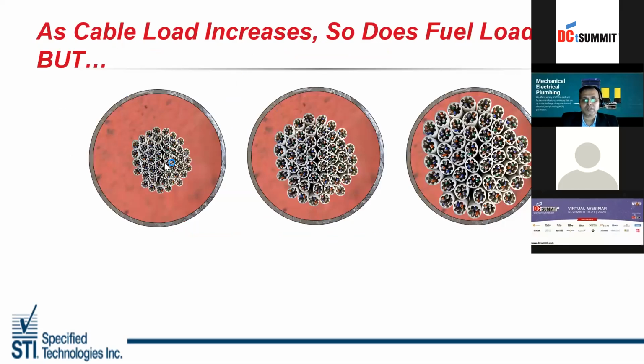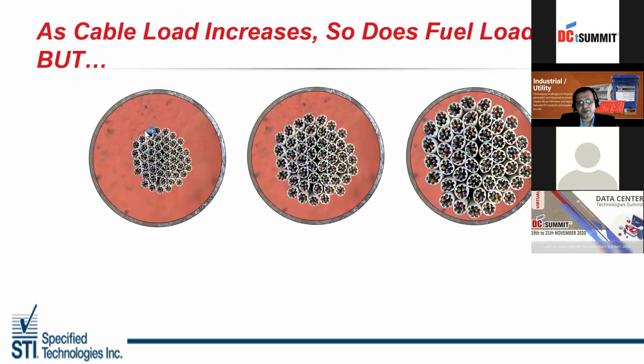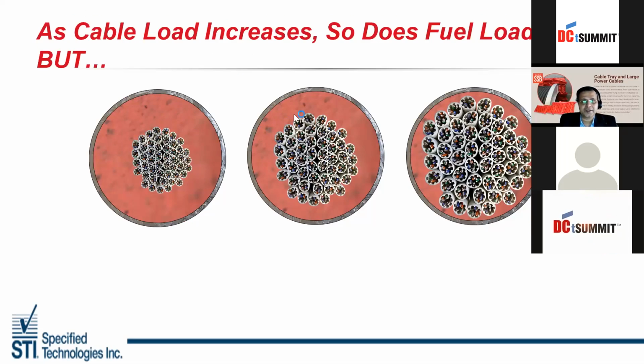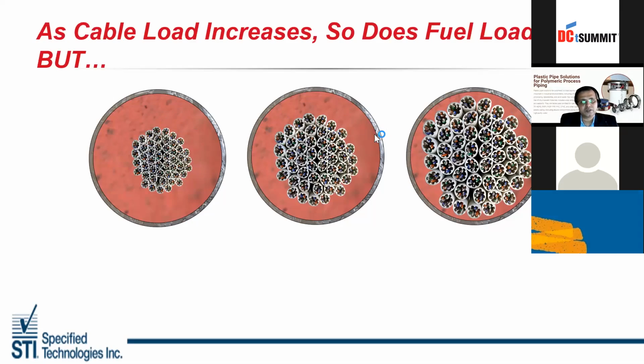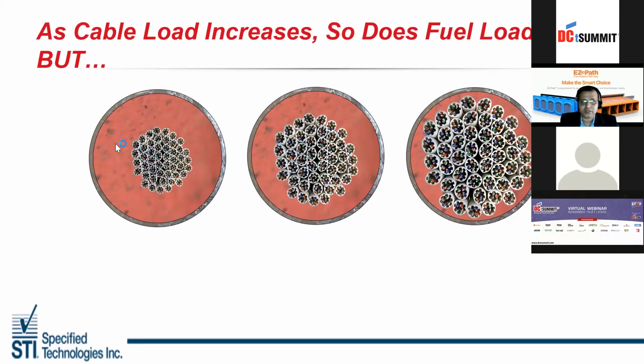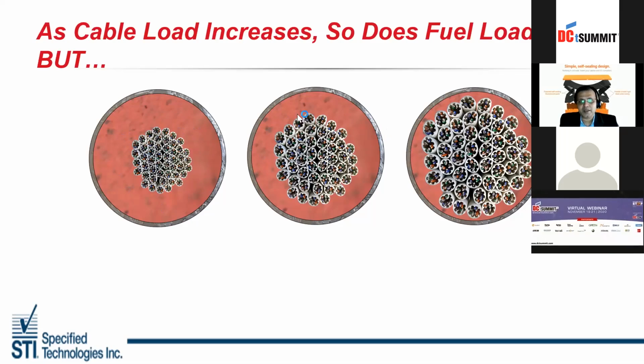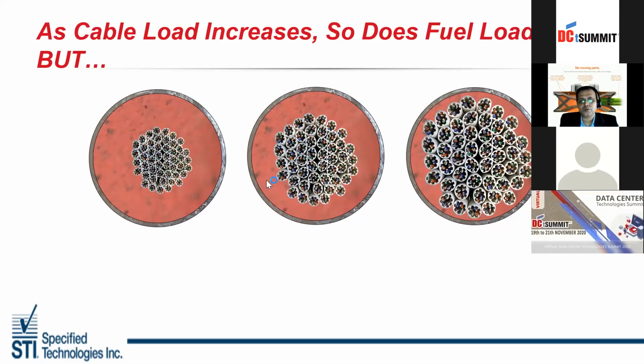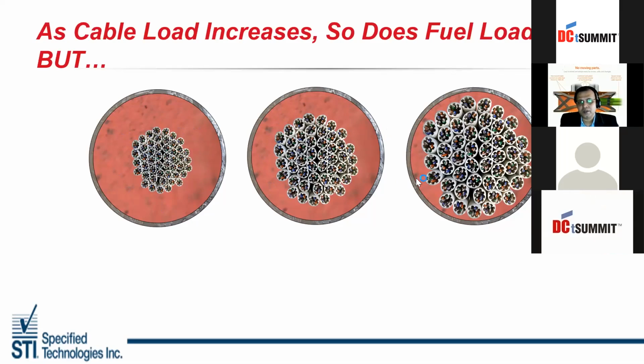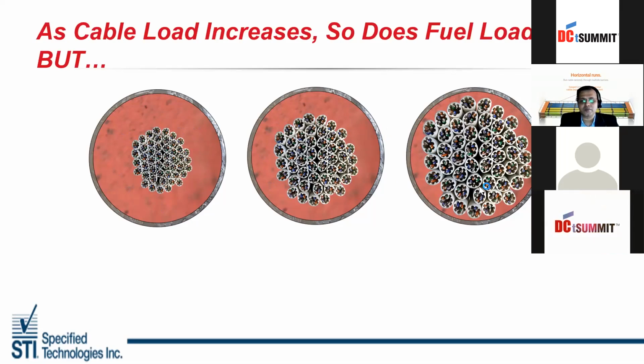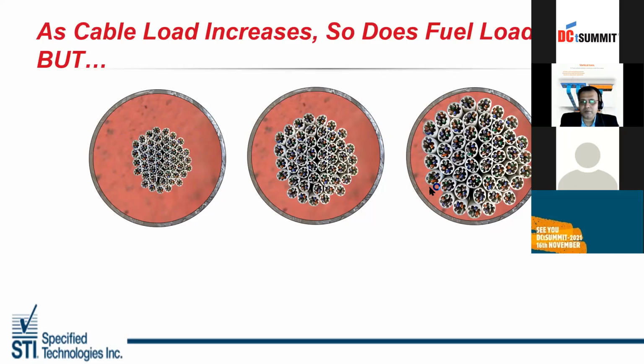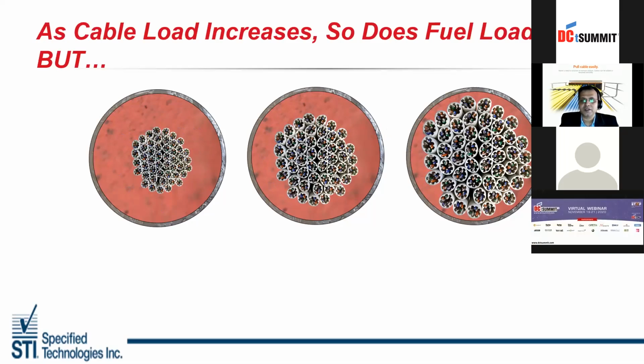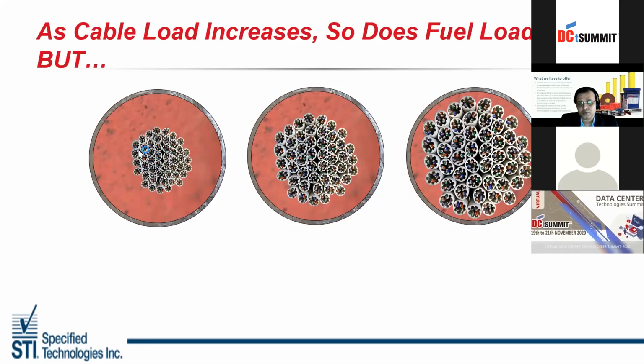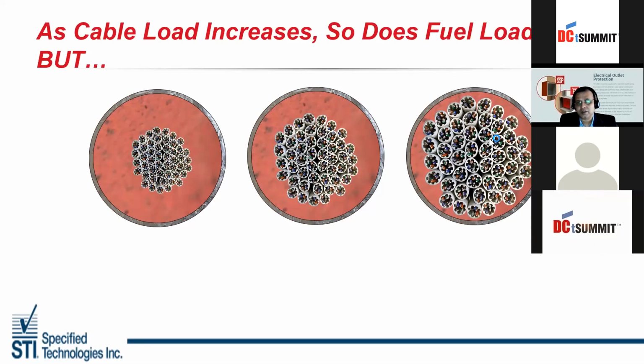This is what happens. You have a sleeve and you have putty installed. The first one is appropriate, it is correct. The second and the third one are very dangerous. The reason: here 16 mm of putty is installed, which is correct for 2 hours of rating. As the cable increases, the sealant thickness also has to go up. Here, this is very dangerous. The cables will burn off within seconds, and the amount of putty applied will fail. The putty has to expand, which is correct for the first scenario towards your left hand side. This is a wrong application.